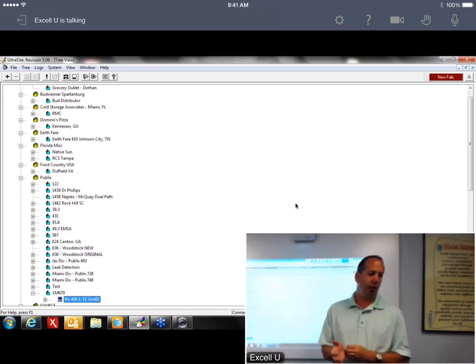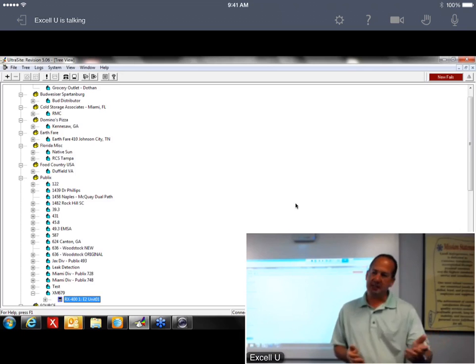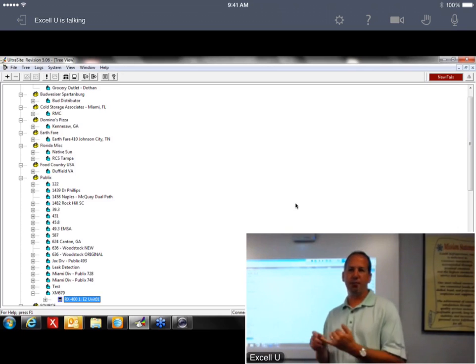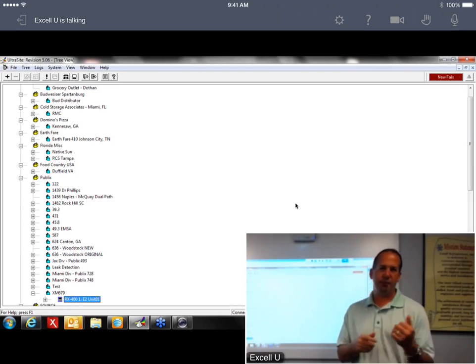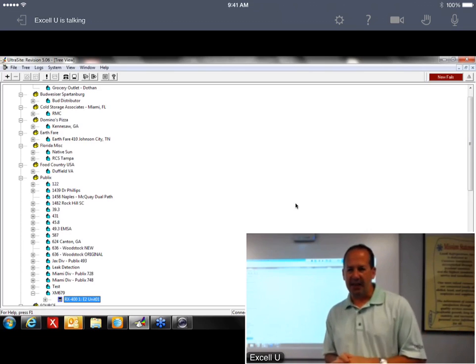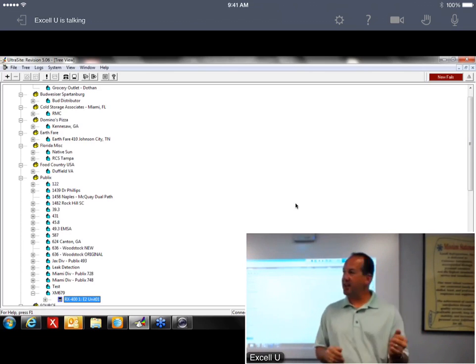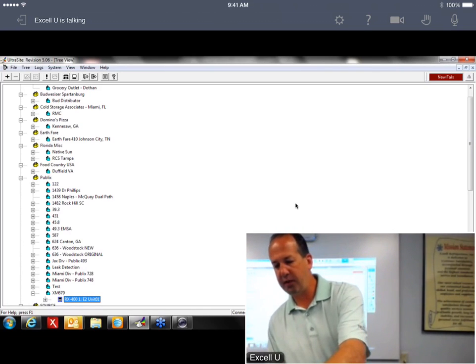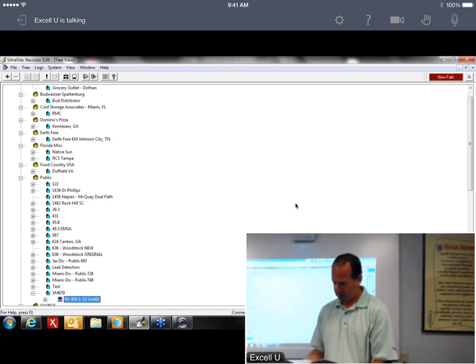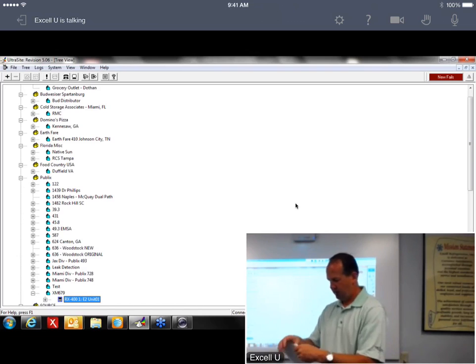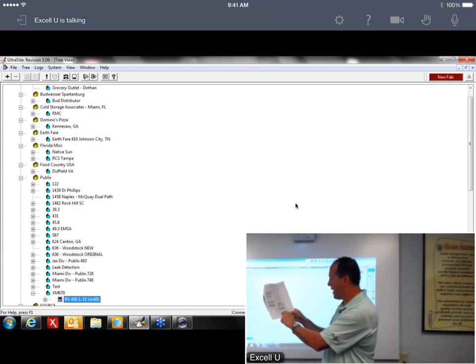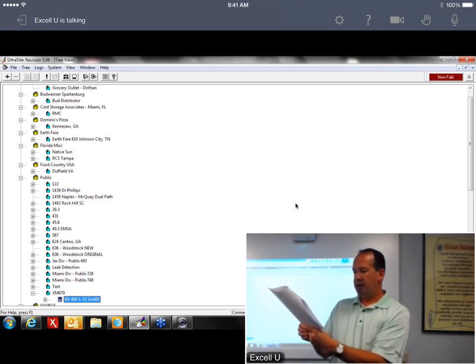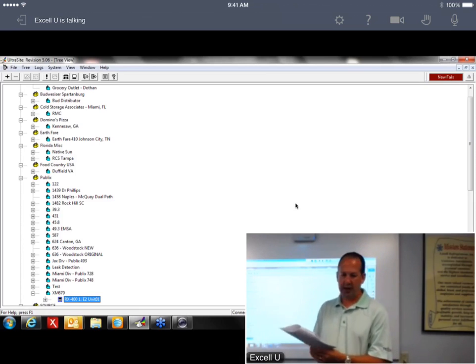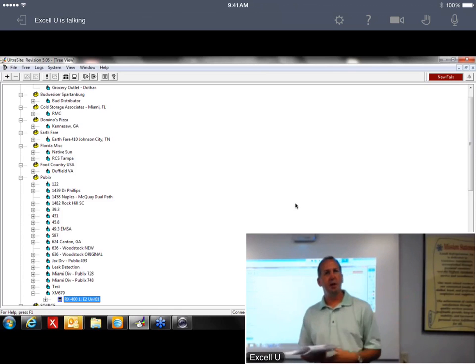One of the things we'll talk about too are our probe IDs. The Dixell identifies probes in the controller as P1, P2, P3, P4, P5, P6. That doesn't mean anything, so I'm going to identify what these stand for. It's also in this sheet on one of the wiring diagrams in the back, I think the one for the walk-ins. This diagram for the walk-ins has all of the inputs down below, and the discharge air is probe P1, or PB1, some say. In the E2, when you're going through setups, you'll see the probes identified as P1, P2. So that's why I want to draw attention to this.